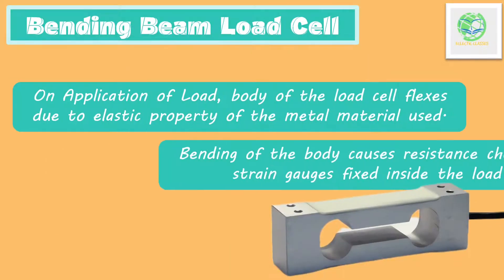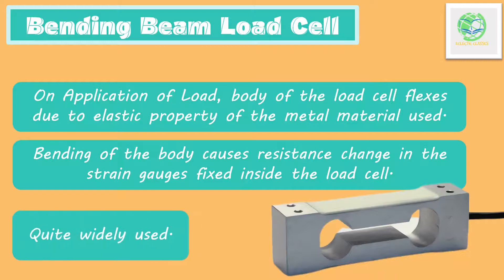Bending beam load cells are quite widely used. In the case of a beam load cell, when a load is applied, the body of the load cell flexes due to the elastic properties of the metal material used in its body. Due to this bending, the electrical resistance of the strain gauges fixed in the load cell changes, enabling us to measure the force applied.